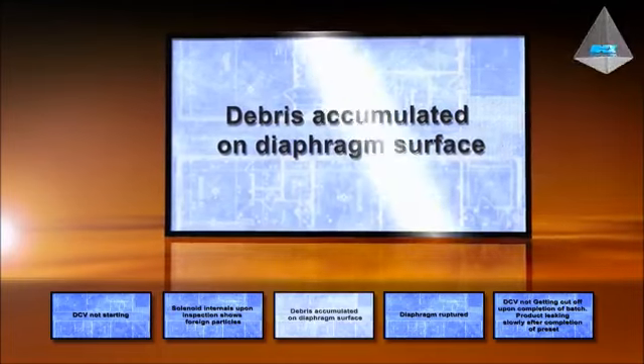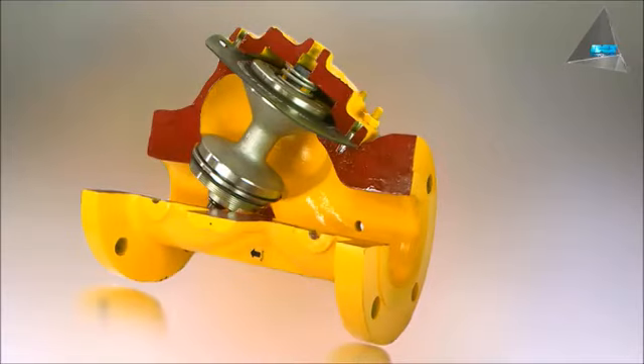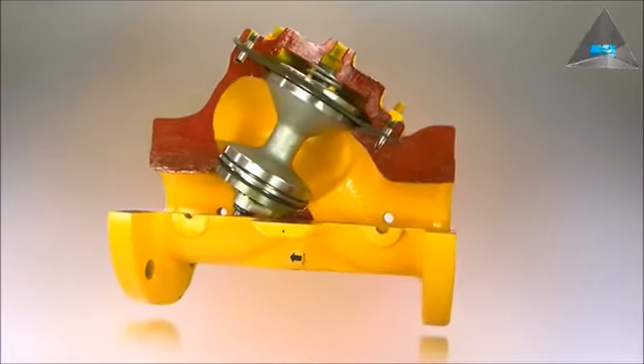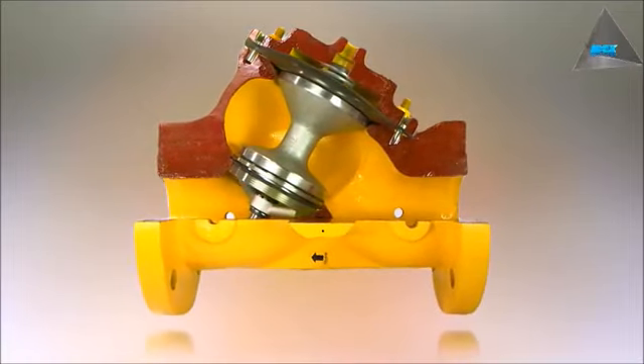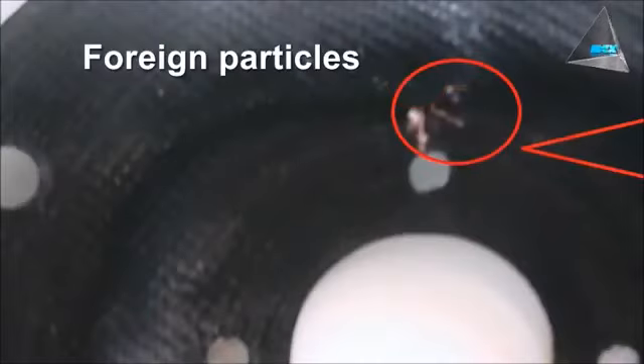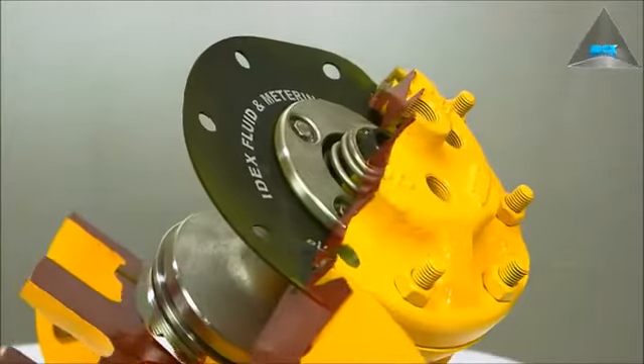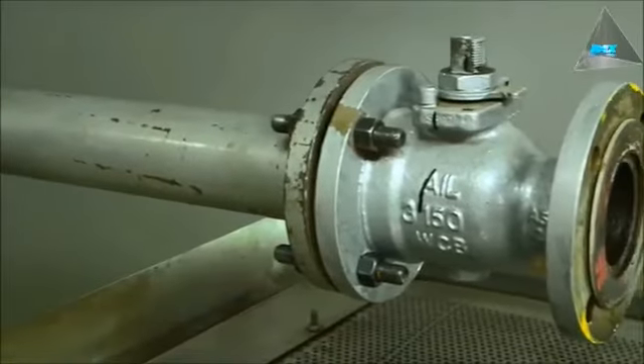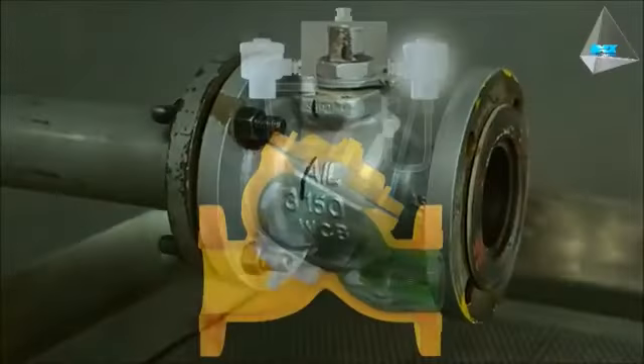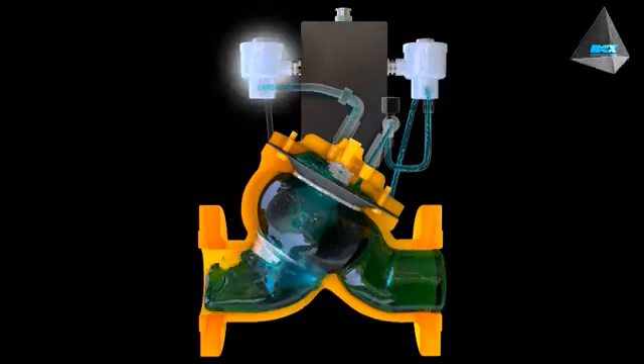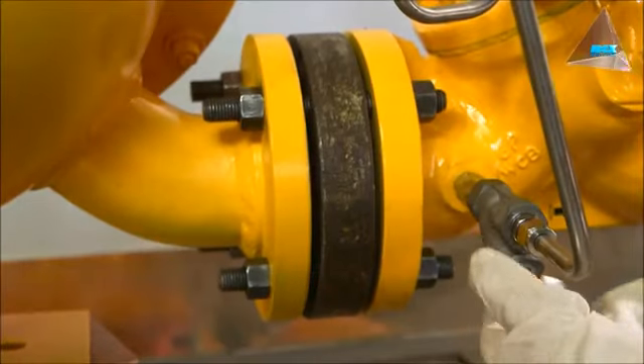Debris accumulated on the diaphragm surface. Solution: check the diaphragm and clean the surface of the diaphragm and the internal parts of the valve. Diaphragm ruptured. Possible cause: diaphragm rupture may be due to transient pressure or foreign particles. Solution: replace the diaphragm. Flush the line with a liquid compatible with the metering system. Ensure that the system is filled with liquid. Clean the valve strainer basket.